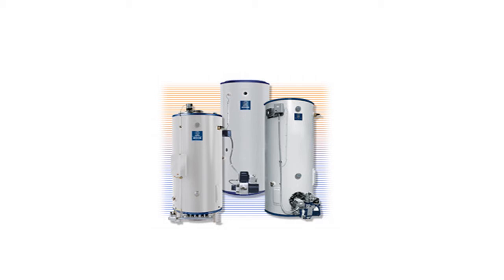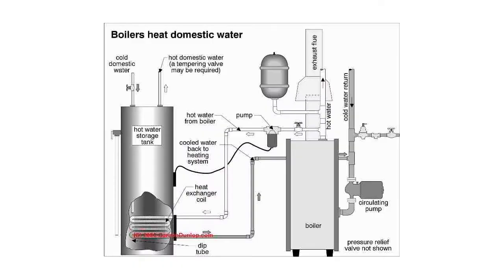Thermostats have a dial for setting the maximum water temperature. Indirect water heaters work like a direct-fired water heater, but instead of having their own burner, the indirect water heater uses the home's boiler to heat the water that passes through a heat exchanger in the storage tank. Indirect water heaters allow the burner to turn off and on less, saving energy, making them the more efficient option than a tankless coil or direct-fired water heater.